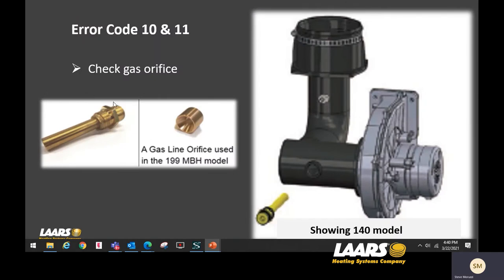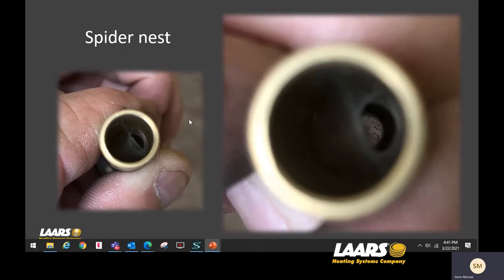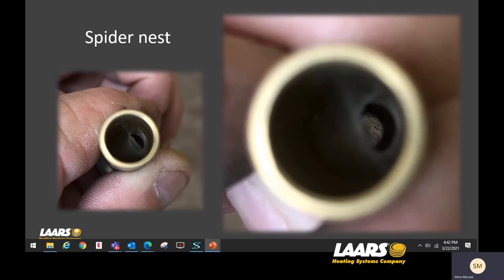Not very common, but if the burner is clean and you have gas and ignition, check your gas orifice — things can get plugged up inside. The longer orifice is for the 140 model and the smaller one is on the 199 models. One winter we had a couple of complaints at startup of the heating season from spider nests — this is more common in a heat-only model because in summer a combi boiler operates for domestic hot water, but heat-only units sit idle. Around the fall, spiders make their webs, and that is enough to restrict the air-fuel mixture so you won't get proper ignition. Also check the combustion air intake — here's an example where a child dropped a plastic Easter egg inside the combustion air vent and it ended up right at the boiler's combustion air intake.